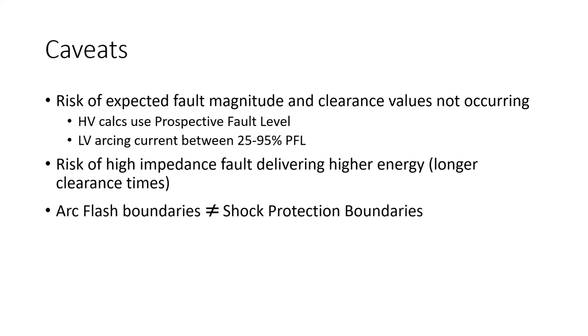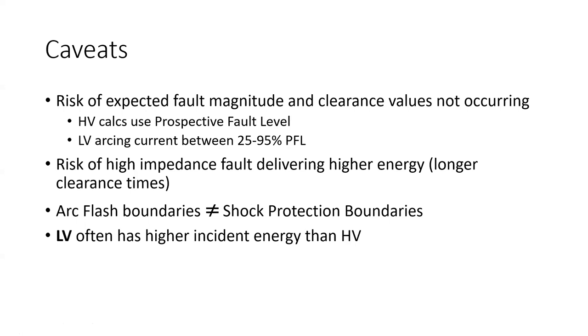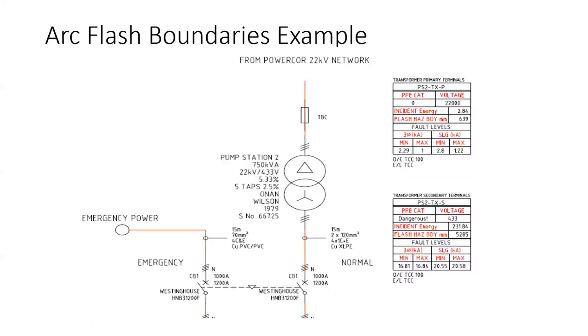Another important point to realize is that arc flash boundaries have no relationship at all to shock protection boundaries. And we'll take a look at an example in the next slide. And low voltage often has a higher incident energy than high voltage. And again, we'll see that here. So this is just for illustrative purposes. I think it's a cutting I got from a project in Sydney.